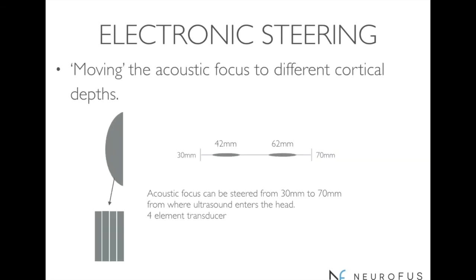As I mentioned earlier, we have this steering range available, which is the range the transducer's focus can be moved—default is 30 millimeters to 70 millimeters from the point where the ultrasound enters the head. We can also do a custom steering range for a case, and you can be quite clever and stimulate just outside the 70 millimeter steering range.